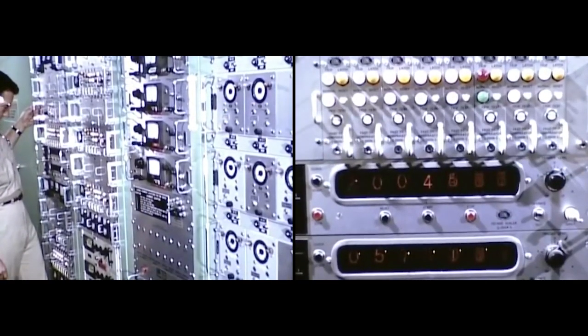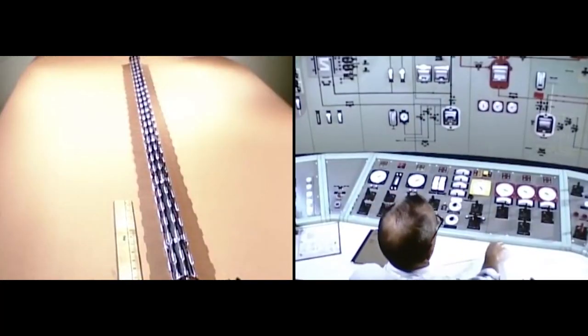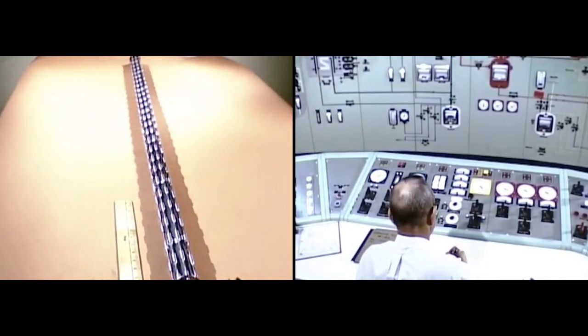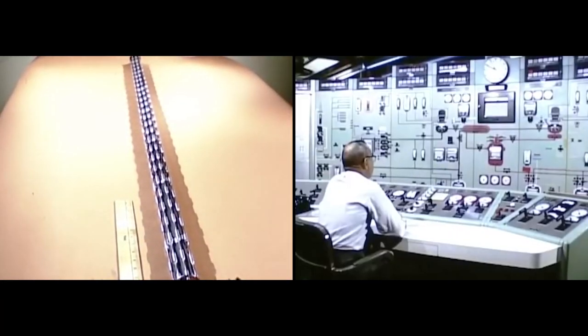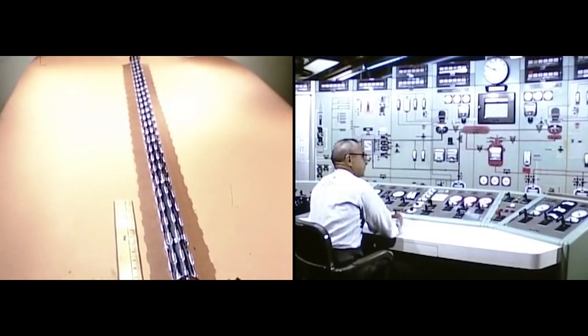The system was dynamically stable at all power levels. Graphite and Hastelloy N specimens, similar to these, have been removed from the reactor core. Examination indicated no deleterious corrosion or structural change after salt had been circulated in the fuel system for more than 6,000 hours.